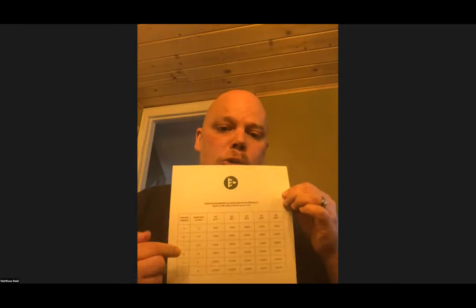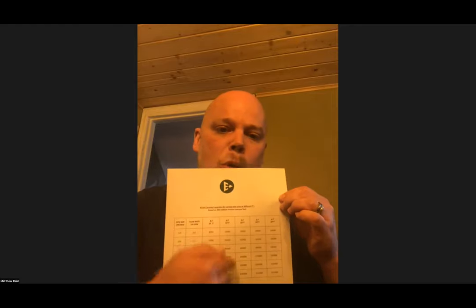What it's going to be is a lot more details and formula. I've actually got it in front of me here. You're going to get a lot more of these type things with charts and graphs. This particular chart that I've got in front of me, I'm not doing a great job at it. I know it's out of focus, and I'm sorry, but this chart is a flow rate chart. It shows me what size pipe I need to carry what BTUs at what delta T. Spoiler alert, 3/4 inch pipe is not the size of pipe you need to carry 150,000 BTUs. I know, right? Crazy. You actually need a bigger pipe than that.